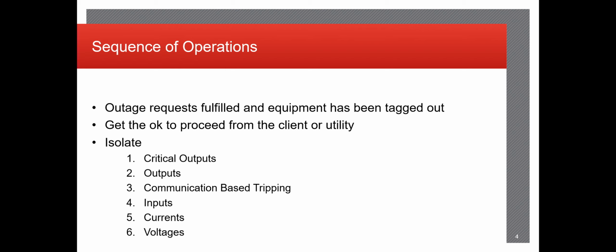Next is communication-based tripping. This is usually any fiber, Ethernet, or any other sort of communication device that may operate a piece of equipment that may not even be at this station. This could be at another station altogether. So removing that gets rid of the risk of misoperating somewhere else. And lastly, that doesn't involve any power flow, would be your inputs. This is anything that the relay may be seeing from other relays, breaker statuses, switch statuses, etc.